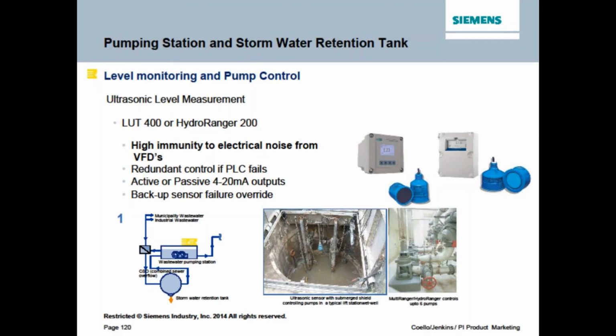So the first thing you might see is a pumping station. For me, if I'm dealing with a lift station or a pumping station, I'm going to want to go with an ultrasonic that has a narrow beam angle. So, we might be able to get as low as 6-degree beam angles in these types of applications. And typically inside a lift station, you're going to have fairly dense foam or a grease layer. And your big concerns are just not a ton of space inside the station. So really good for ultrasonic, or if you wanted to use a high frequency radar with a narrow beam angle, that's a possibility as well, just depending on how much condensation, moisture, humidity you have inside the station.